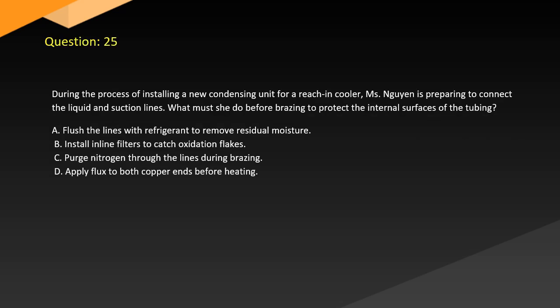Question 25. During the process of installing a new condensing unit for a reach-in cooler, Nguyen is preparing to connect the liquid and suction lines. What must she do before brazing to protect the internal surfaces of the tubing? A. Flush the lines with refrigerant to remove residual moisture. B. Install inline filters to catch oxidation flakes. C. Purge nitrogen through the lines during brazing. D. Apply flux to both copper ends before heating.